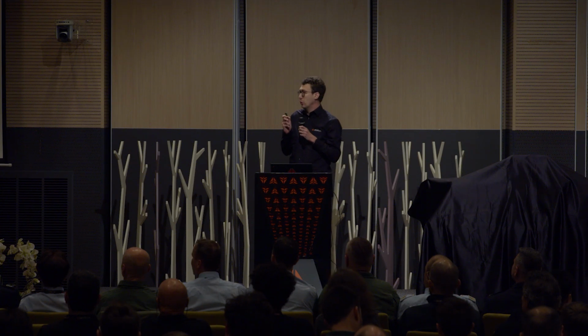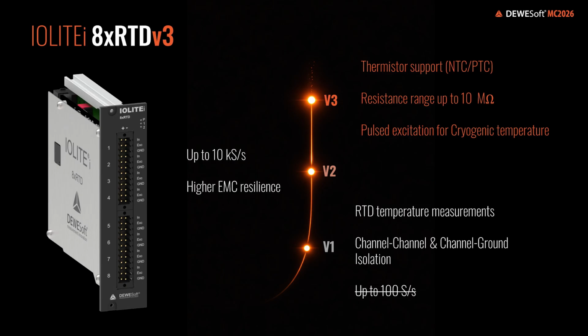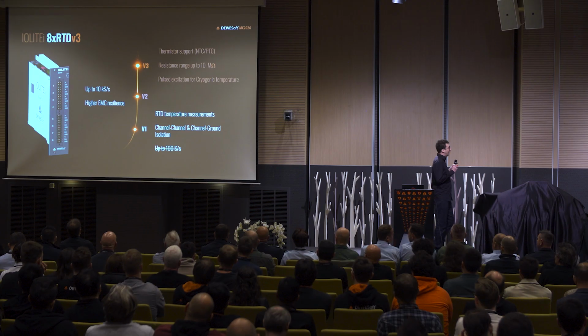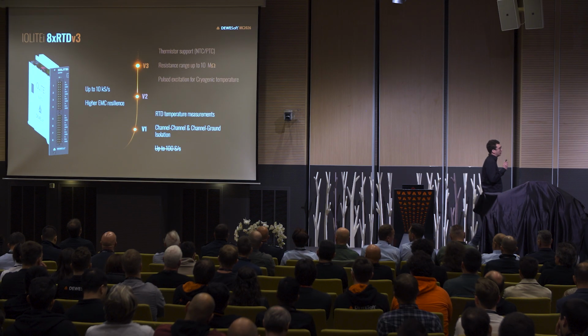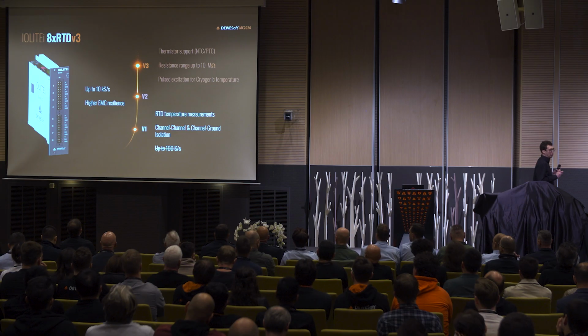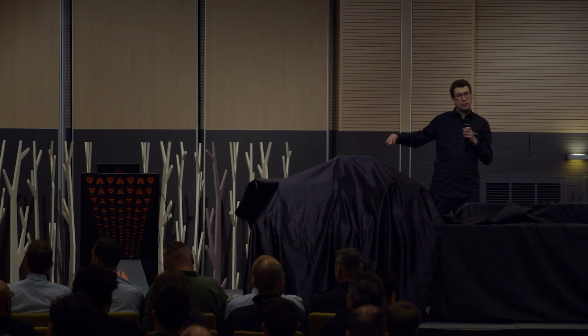We wanted to create a truly universal resistance temperature device. This one is capable of using any kind of thermistor sensors, such as NTC and PTC. It can measure up to 10 megaohms of resistance. And with pulse excitation, you have the ability to do cryogenic temperature measurements—really low, like minus 150 degree measurements.